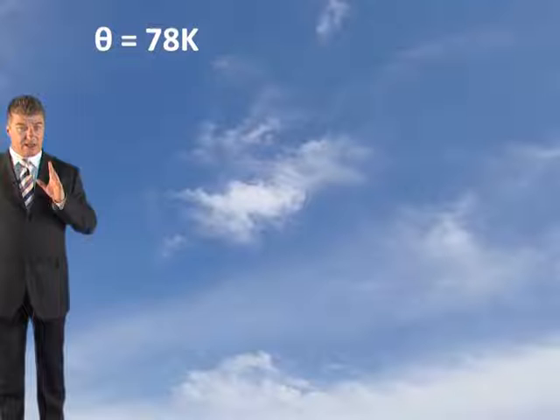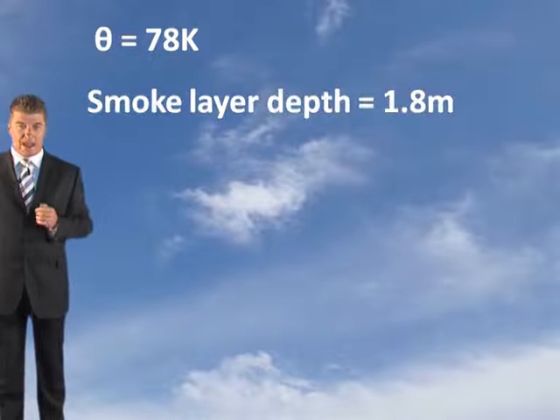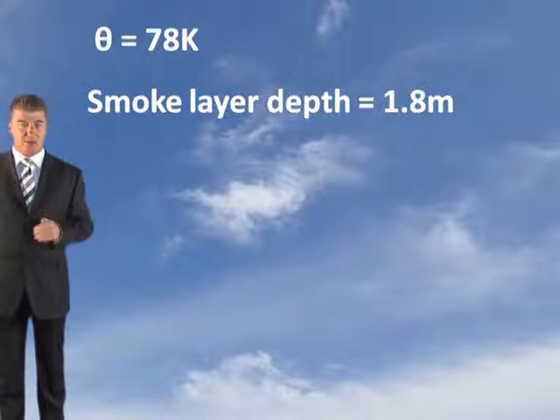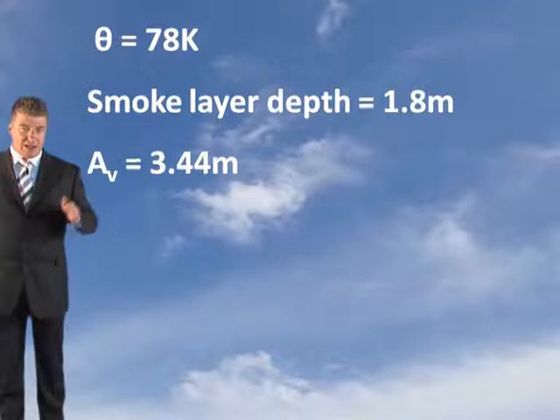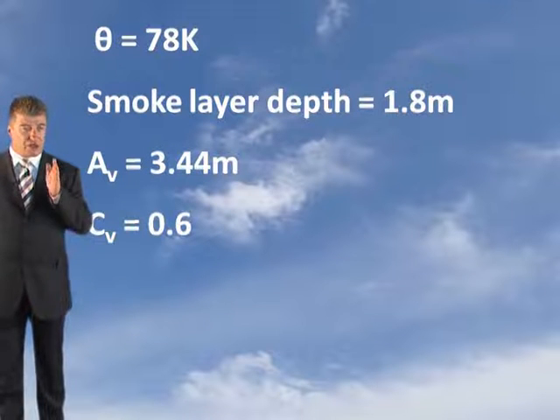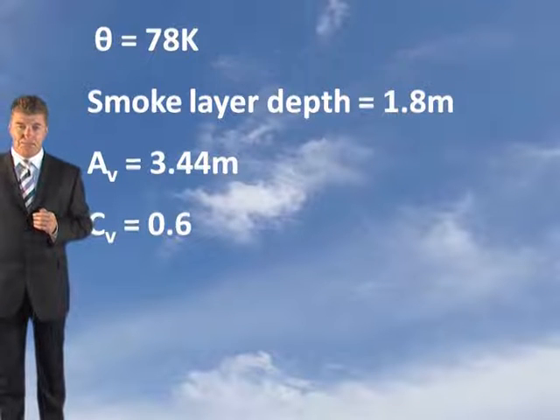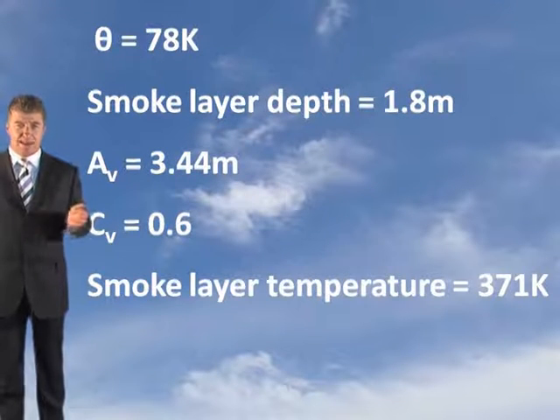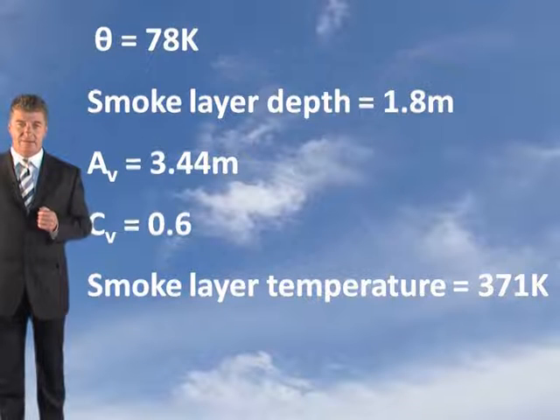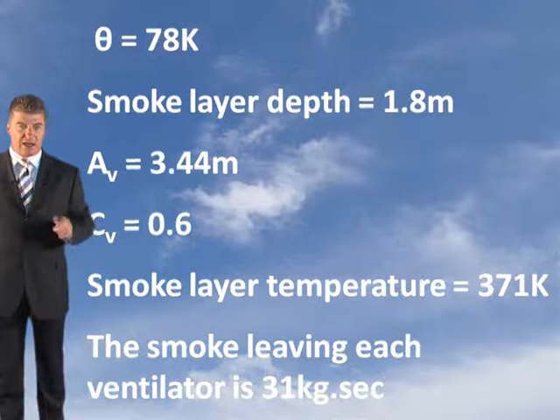Your theta value, your temperature increase, is worked out at 78 degrees Kelvin. And your smoke layer depth is 1.8 metres. So it's got quite a narrow smoke depth. The aerodynamic vent area of each vent is 3.44 metres and the ventilator has a coefficient of 0.6.